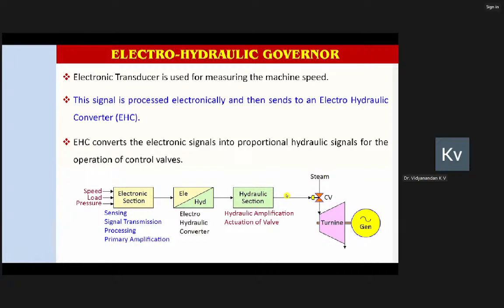Whereas in the Sipat 660 megawatt, India's first 660 megawatt unit number 1, the hydraulic governor has been completely discarded. Only electro-hydraulic is there. So the sensing, everything, is done electronically, and for the operation of the stop and control valves, we have the hydraulic actuators.